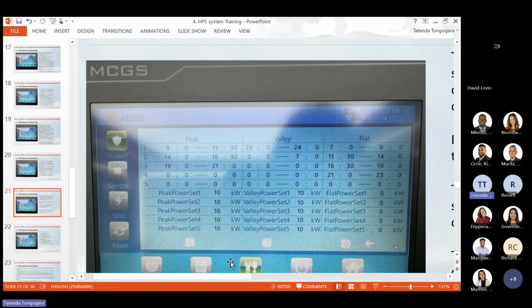So this is the peak values where you set your times. If the peak time is between 9 and 11:30, you set it like this. And then the valley time, this is when you can charge with grid. At this time, you only discharge with the battery. At the flat time, your BMS is just in a waiting mode. It's neither charging nor discharging. It's just in waiting mode.